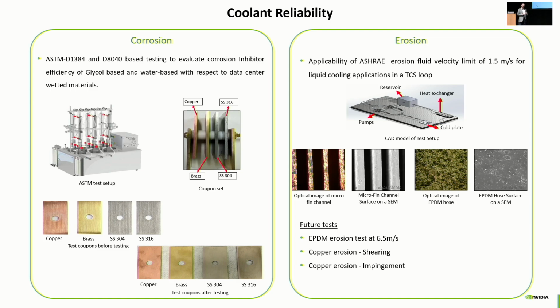One of the challenges of liquid is fluid velocity. As opposed to air, which doesn't eat anything, liquid eats—if you have copper in contact with liquid and it's impinging, it can eat away some of your copper, especially at higher flow rates. So we're researching how fast we can push this liquid inside these skived fin cold plates, which have a 100-micron fin structure to remove heat, and what type of material works best.